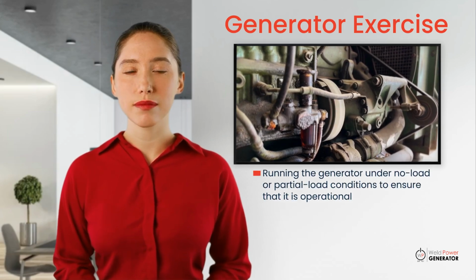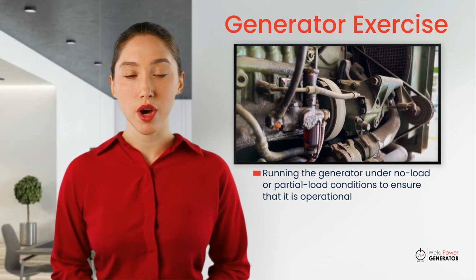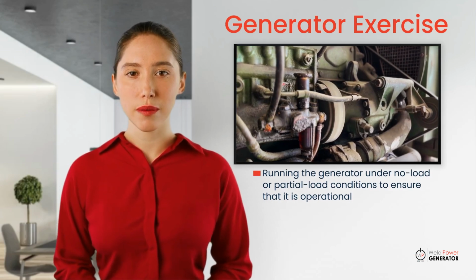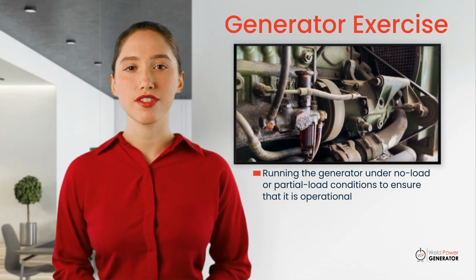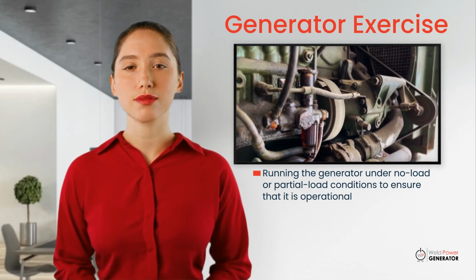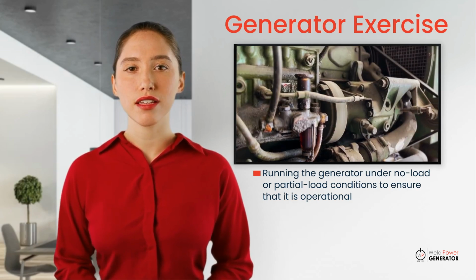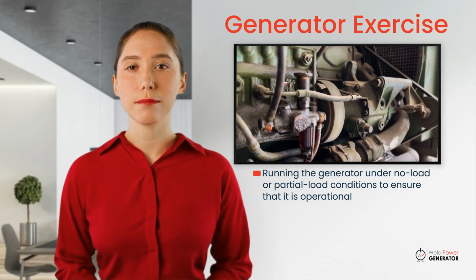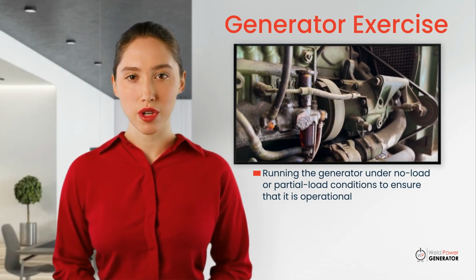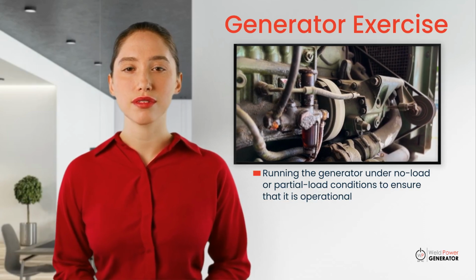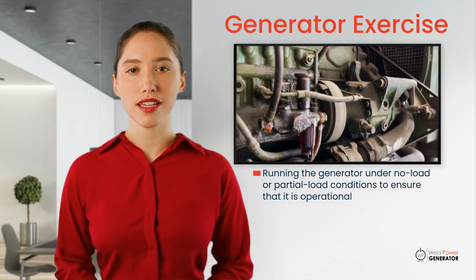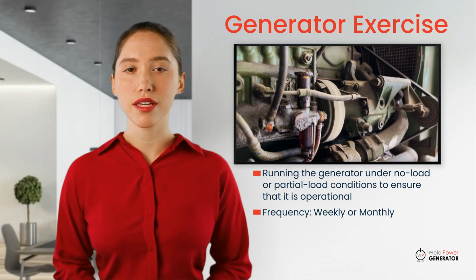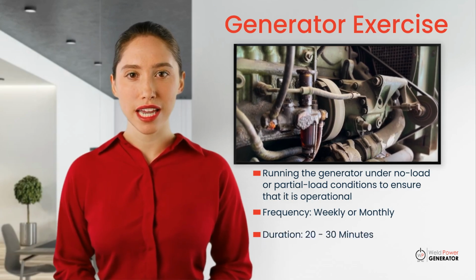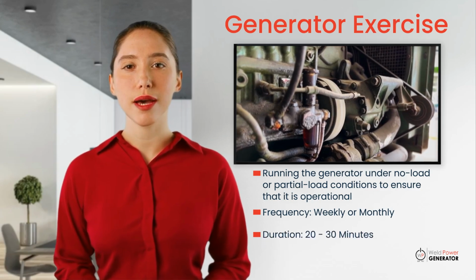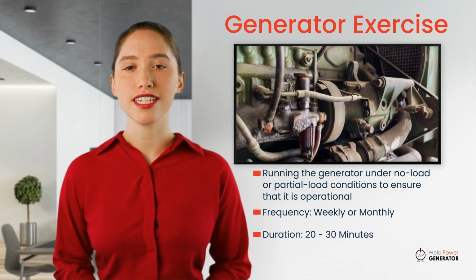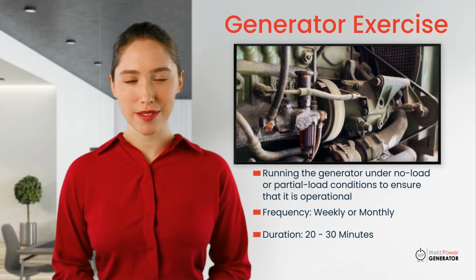Generator exercise is the process of running your generator under no load or partial load conditions to keep it operational. This helps to circulate fluids, lubricate moving parts, and prevents moisture and contaminants from building up. It is recommended to have personnel monitor this process for leaks, unusual noises, or other visible issues that could indicate a problem. The exercise should be performed weekly or monthly, typically for 20 to 30 minutes. Regular exercise prevents battery discharge and ensures the generator can handle a load in case of an emergency.